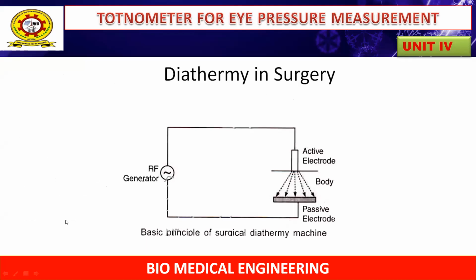So this is the basic principle of the surgical diathermy machine. In surgical diathermy, the frequency of the current is in the range of 1 megahertz to 3 megahertz. The basic principle, shown in this picture, is due to the difference in current density between two electrodes. Here we have one active electrode and one passive electrode.